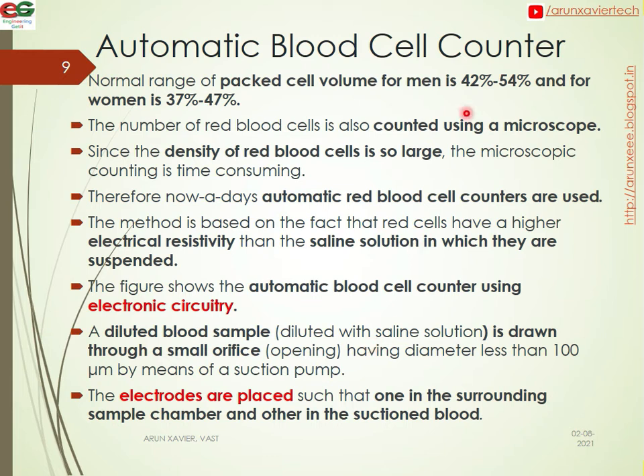The number of red blood cells is also counted using a microscope. However, since the density of red blood cells is very large, microscopy counting is time-consuming. Therefore, automatic red blood cell counters are used. The method is based on the fact that red blood cells have higher electrical resistivity than the saline solution in which they are suspended.